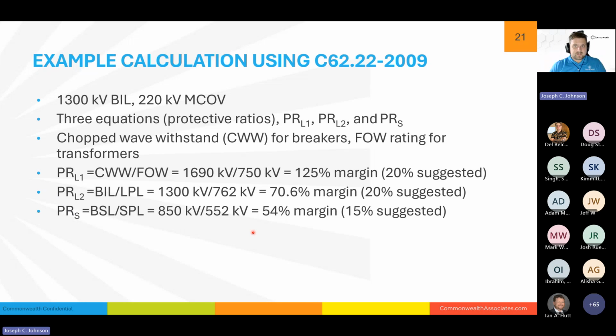So using C62.22 is a great method of figuring out if you're sized appropriately and you have correct protective margins. Reminder, this is a 1300 kV BIL system and a 220 kV MCOV arrestor. So there are three real equations. This is a specific kind of example we're giving here. There are all kinds of permutations on how these equations work, what values are used, depending on the number of lines coming into the system and the number of transformers in the system. This is kind of a general introduction. There's a lot of material. I highly recommend reading into the standard if you want to learn more about specifically testing your case.